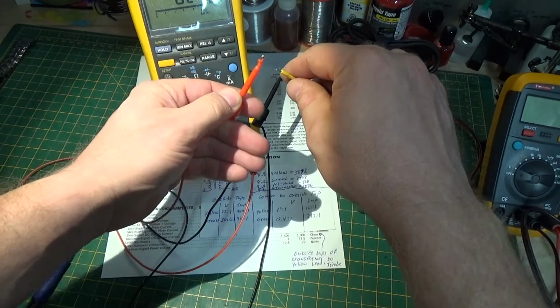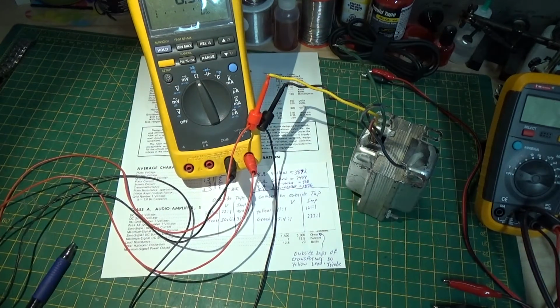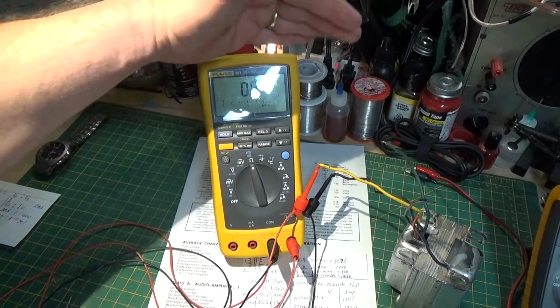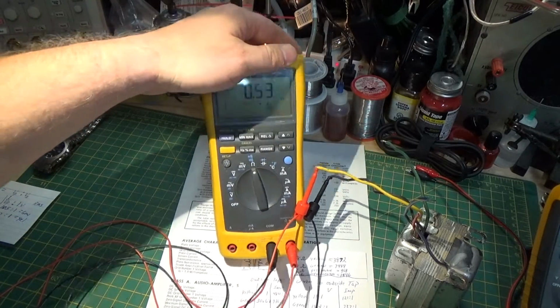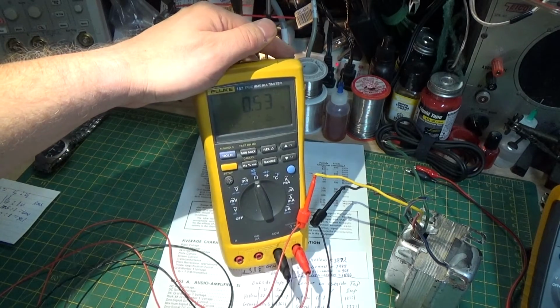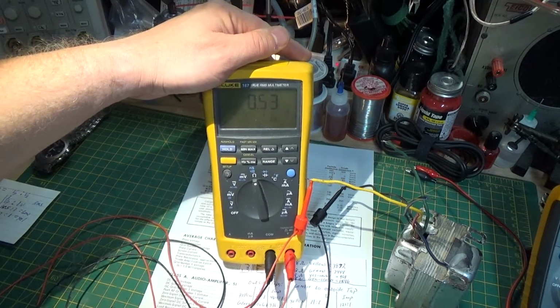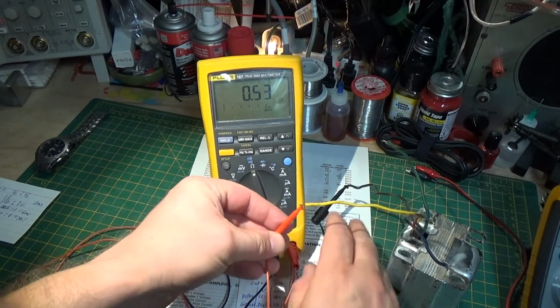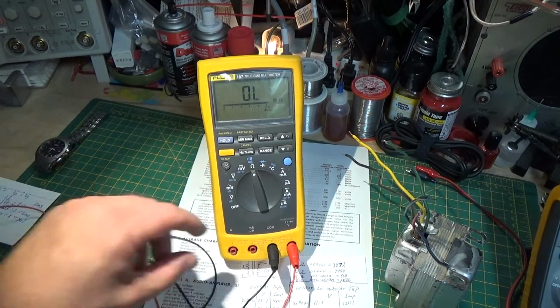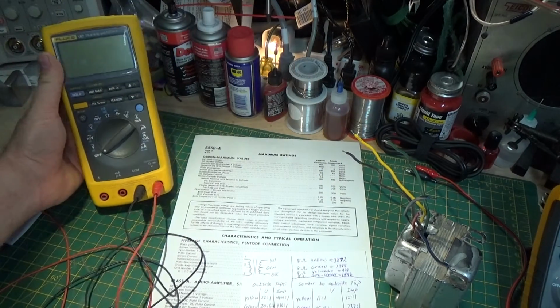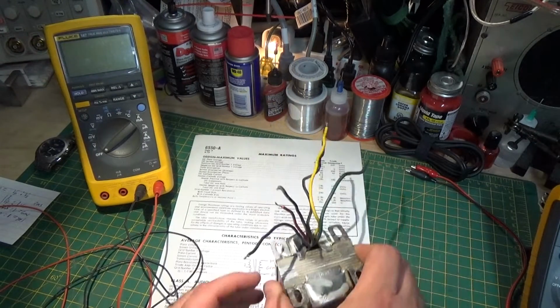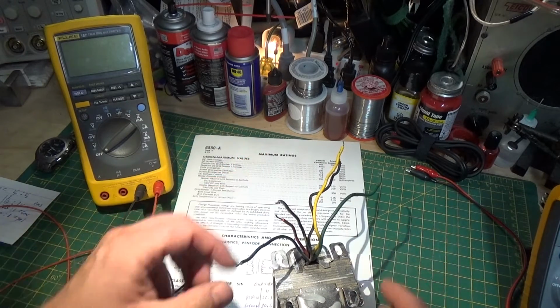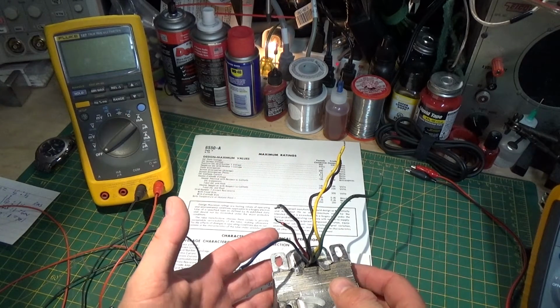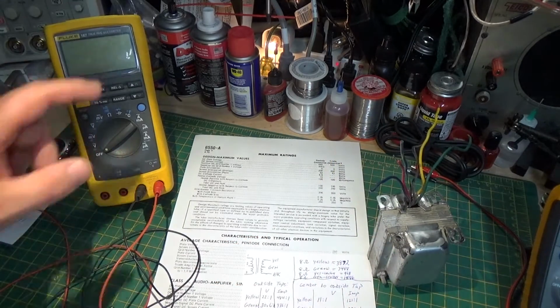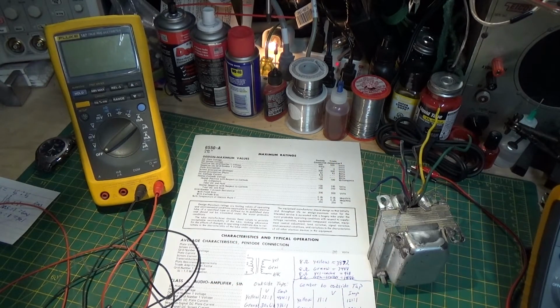But when you look at this, what do I got? Can you see that? Half an ohm, that's all we're getting. So the DC resistance of this has nothing to do with 8 ohms, 4 ohms, anything — it's a half of an ohm. And if this were a different transformer, with a different core material and a larger winding and larger diameter secondary winding wire, it may read different than that and still be an 8 ohm winding.